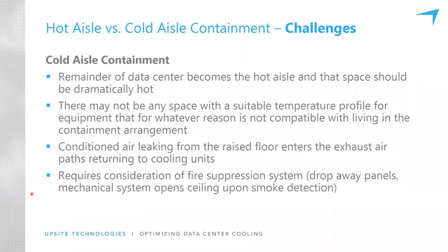Cold aisle containment challenges: the remainder of the data center becomes hot, as I mentioned. It really becomes an uncomfortable space to open the door to and to walk around. There may not be a suitable temperature profile for equipment that is not compatible with the hot and cold aisle configuration. So that standalone equipment is going to be out in a hot space and it's going to be a little harder to cool.